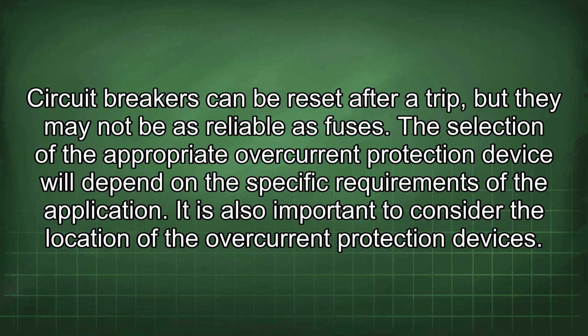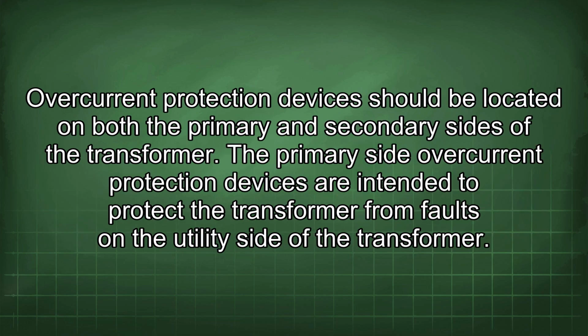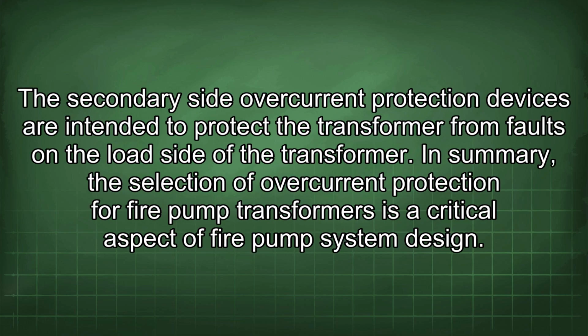It is also important to consider the location of the overcurrent protection devices. Overcurrent protection devices should be located on both the primary and secondary sides of the transformer. The primary side overcurrent protection devices are intended to protect the transformer from faults on the utility side of the transformer. The secondary side overcurrent protection devices are intended to protect the transformer from faults on the load side of the transformer.